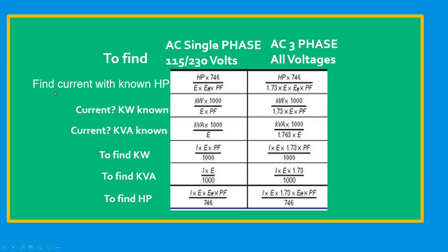For example, find the current with known horsepower. If we are going to find the current with a known horsepower, for example, seven horsepower. So we have seven horsepower here. We're just going to multiply it with 746 because we know that one horsepower equals 746 watts.